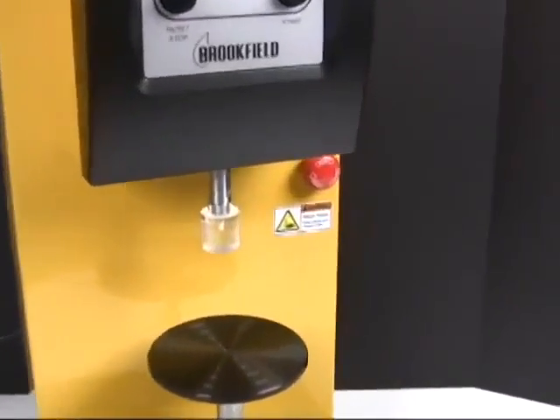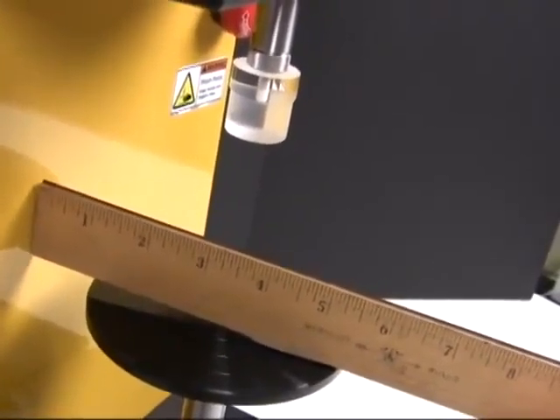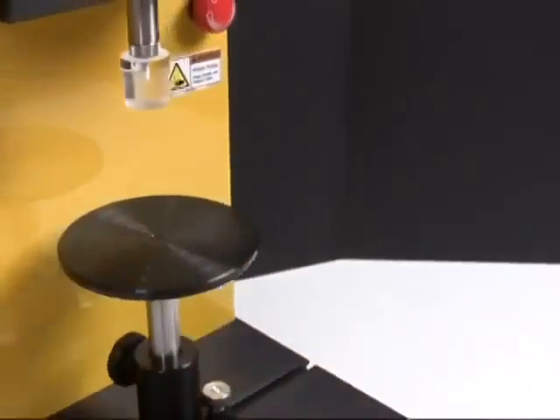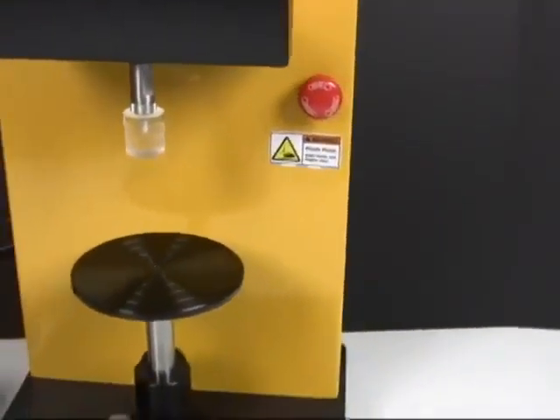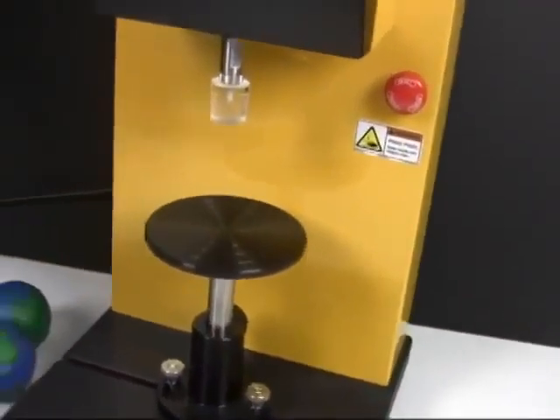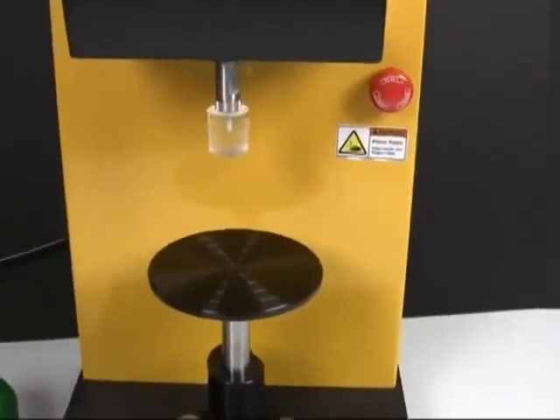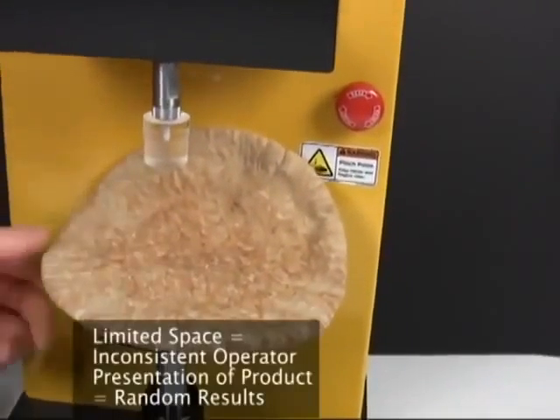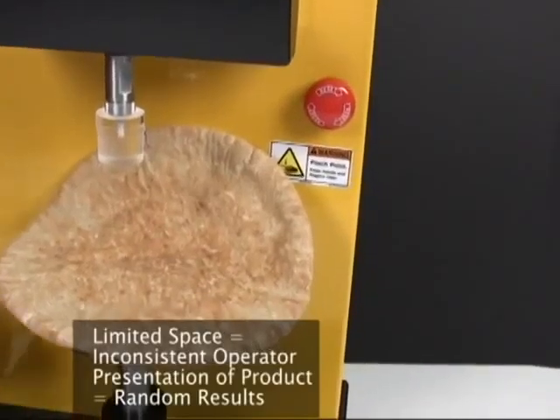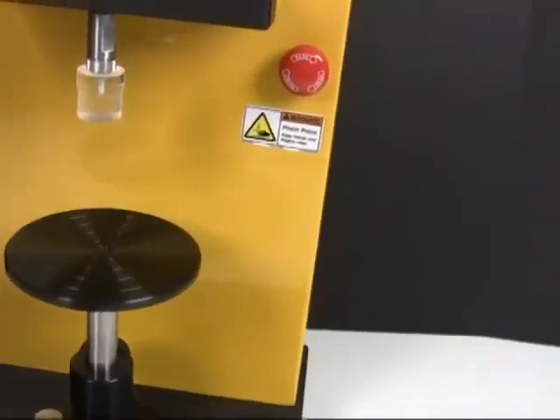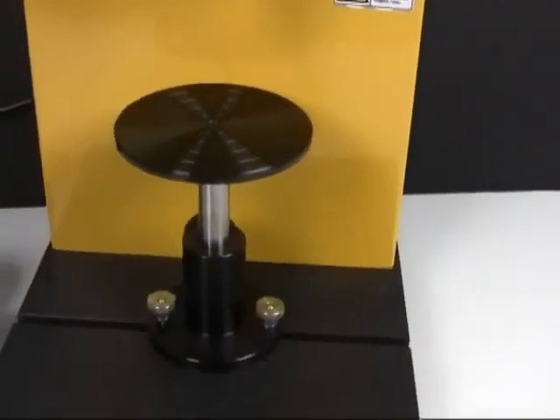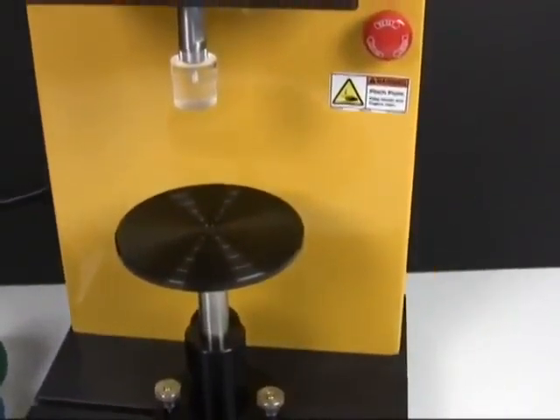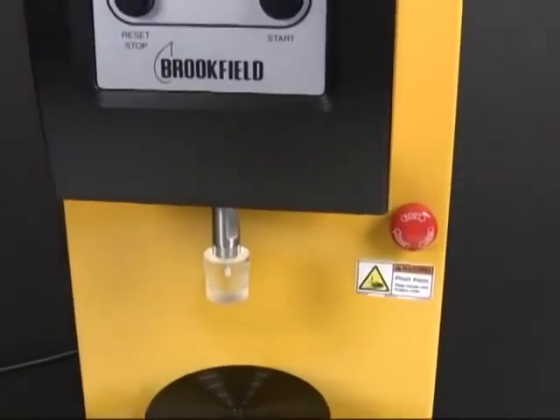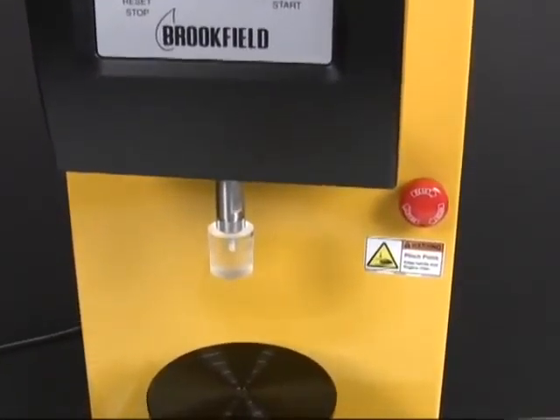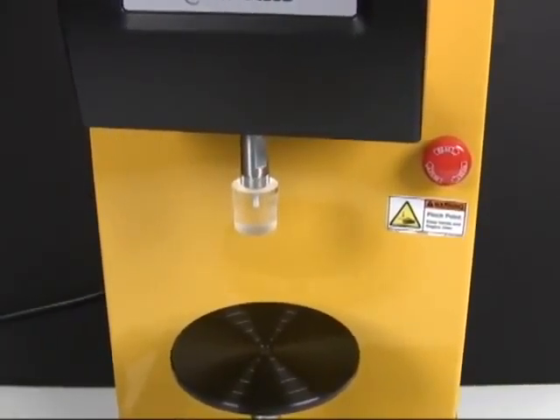The probe is only 3 inches from the back wall as well. You can't test products that don't fit. So any wide object, such as a pita pocket or a tortilla, you actually end up having to either cut them up before you test or fold them up against the back wall so you can still get the center. In terms of an operator's perspective, that's a pain. The instrument also doesn't come with calibration hooks or extenders when you buy it with the default rotary table option. This is pretty inconvenient when you go and try and run tests.